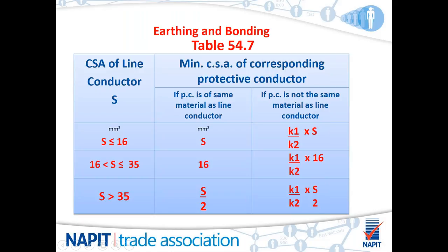In the event that you are installing a line conductor where the protective conductor is not the same material, such as if you were to install a steel wire armoured and use the armourings as earth, or you were using conduit as a means of earthing, then you would look to the formulas in this final column to work out essentially what your conductor size is.